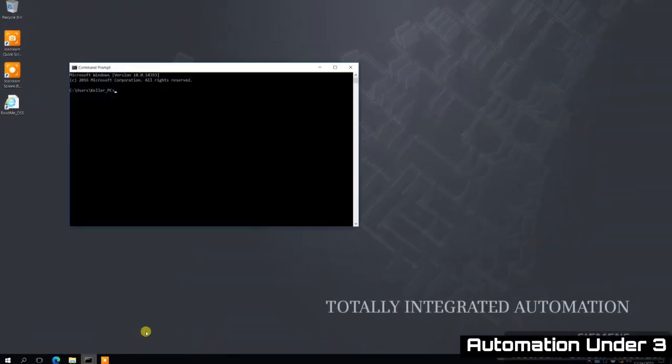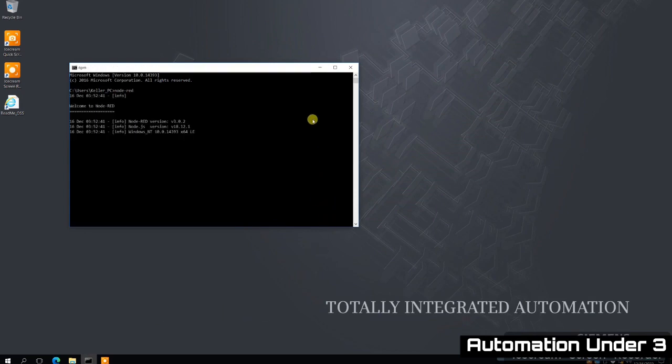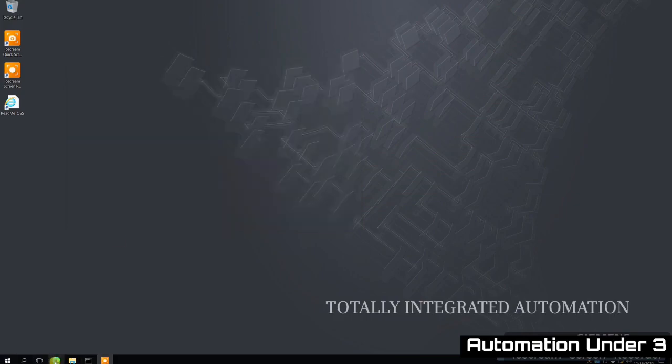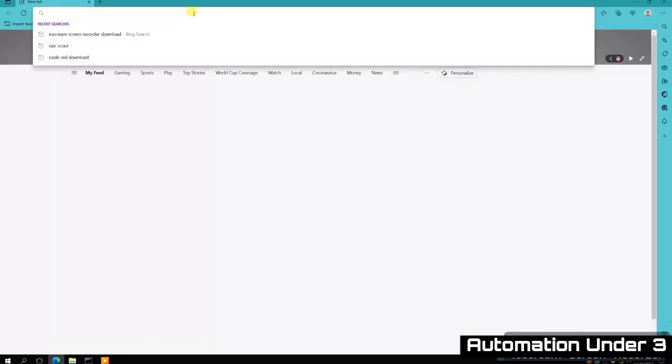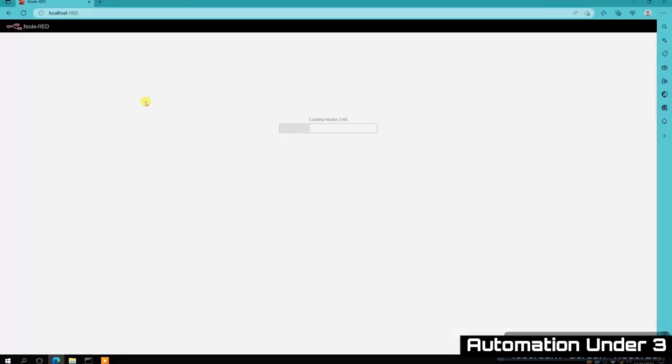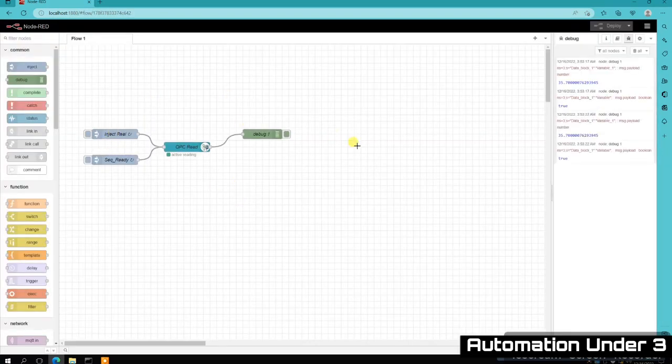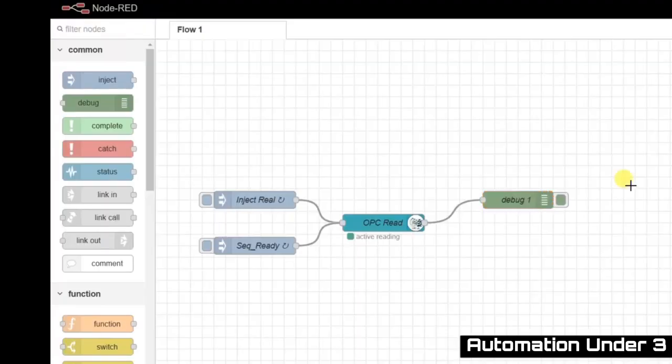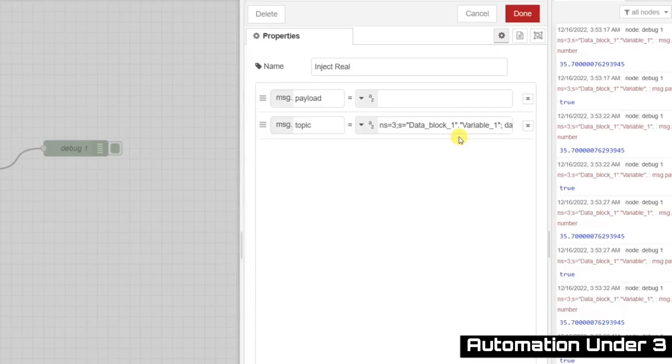Here we are on the IPC side. I've downloaded the Node Red application and all the different palettes needed for OPC UA communication. From there it was pretty simple. You inject, which is a way of selecting the tags that you want to see. So I injected two different tags.